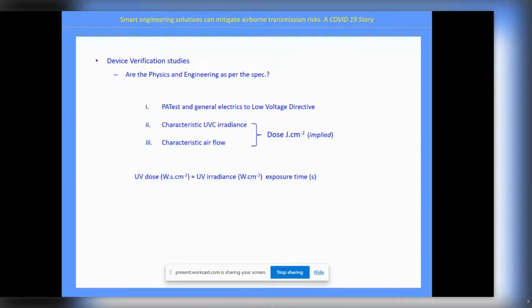So first thing, PAT test. Of course, it needs some sort of electrical test, doesn't it, to show it's sanitary in that regard, and we'll just use the low voltage directive. As clinical engineers, we would like more, but that's the very, very minimum. But these devices are going to say it produces a certain UV irradiance or photon power, and it's going to produce a certain airflow. Well, if you multiply the irradiance by the airflow, you get a dose. So they'll be implying a dose. Okay. Can this dose be measured? If so, dose okay, PAT test okay. This is a verifiable device.